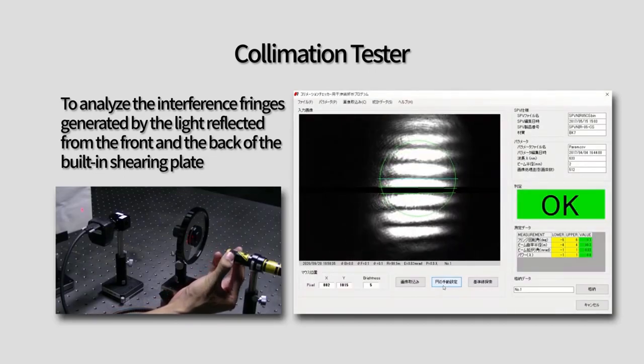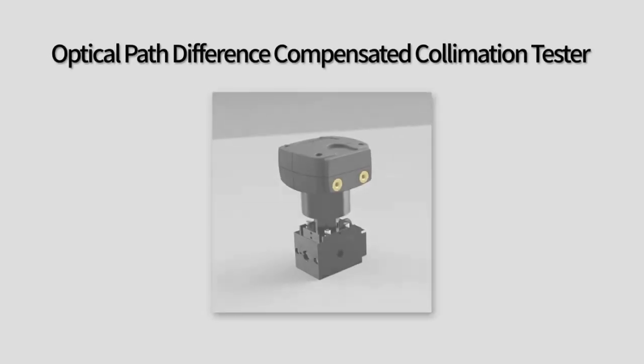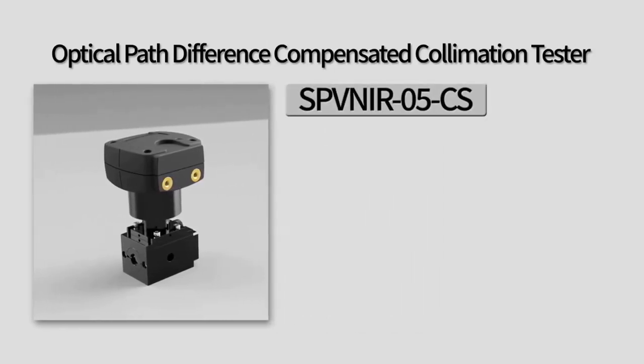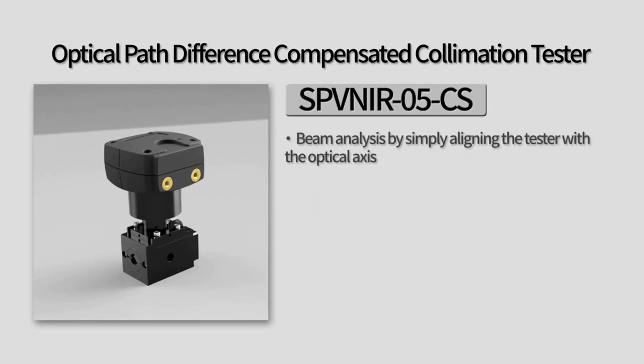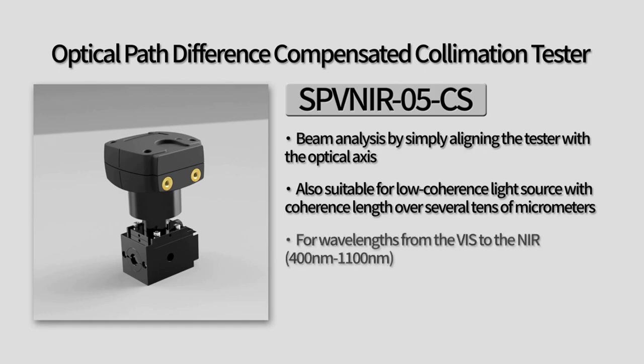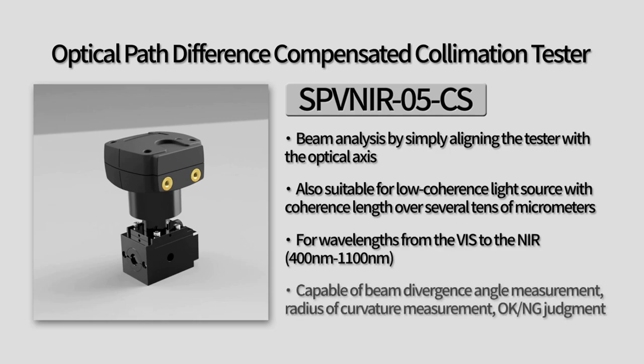The OptoSigma electronic collimation tester, SPVNIR-05-CS, offers several useful features. Beam analysis can be performed by simply aligning the tester with the optical axis, making it convenient and easy to use. It's also suitable for low-coherence light sources with coherence lengths over several tens of micrometers, and it's capable of measuring beam divergence angles, radius of curvature, and providing pass-fail judgment.